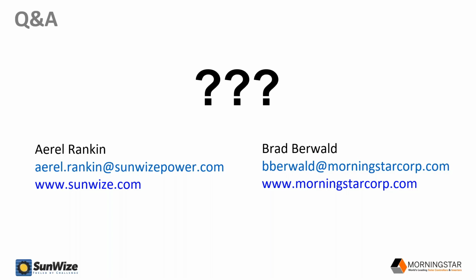The downside is that they had to fly a PE out to every installation to do that field certification, which was very expensive. So for the next round of system installations, that client started to think about achieving a system level Class 1 Division 2 certification, because if the entire system and assembly had that certification, you could bypass the field certification and save the money and expense of bringing a PE out to a field site. That's a specific example we've seen where a client shifted from C1D2 certified components to a C1D2 certified system, driven by internal cost control on their end.